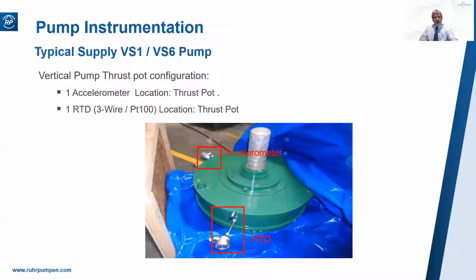This is the thrust pot on a vertical pump, VS1 or VS6. European and Asian motors generally don't take thrust loads, so we have to use a separate thrust pot, which is what I'm showing here. Of course, American motors are designed to take thrust loads, so you don't need this separate thrust pot. Your bearing monitoring would then be in the motor. But if you have a thrust pot, this is what you might well get: an accelerometer on one side and here an RTD.